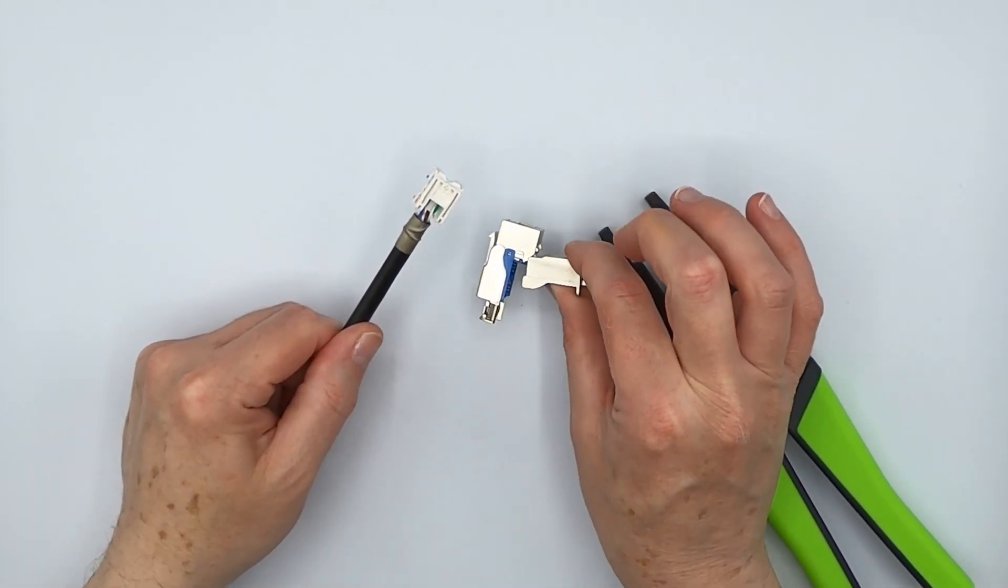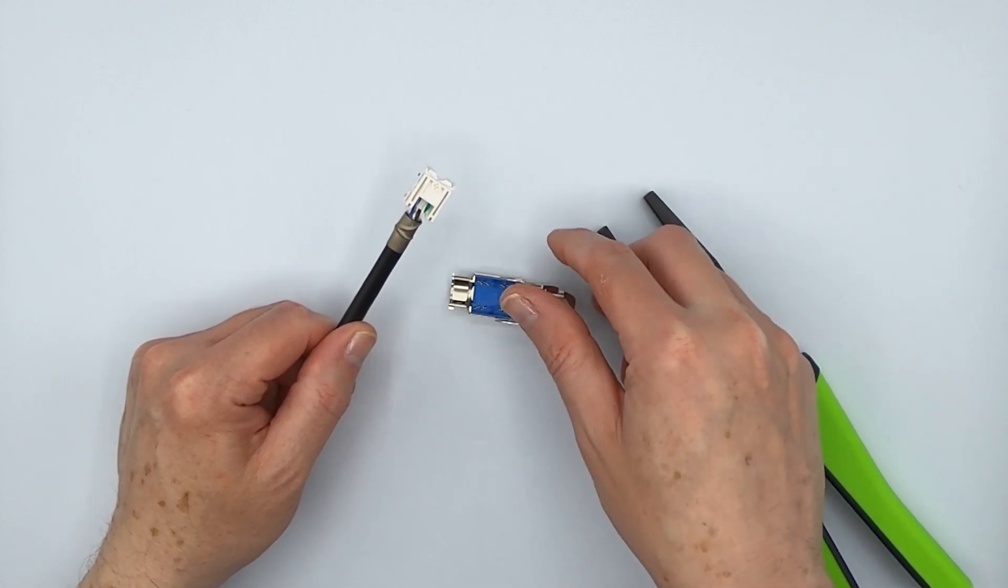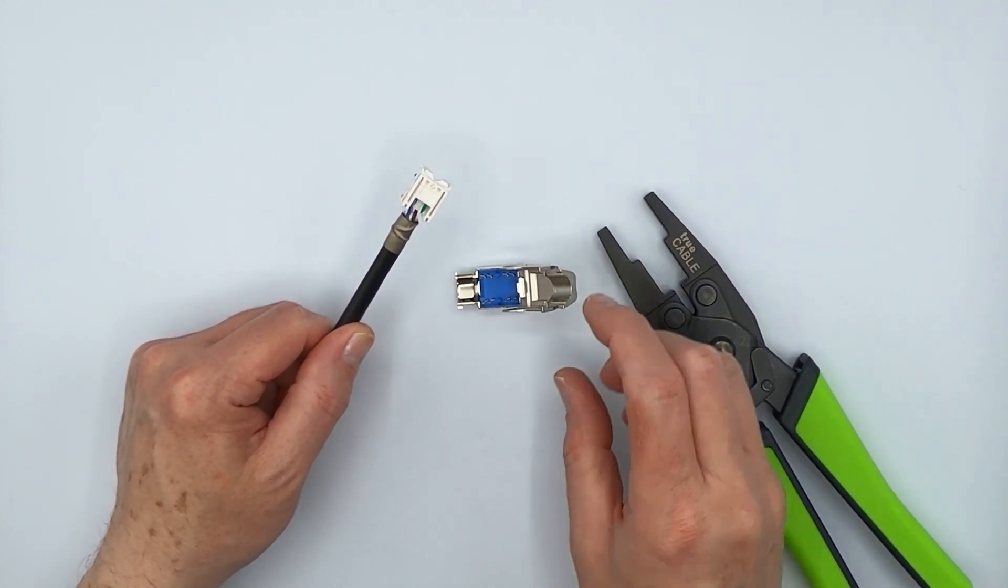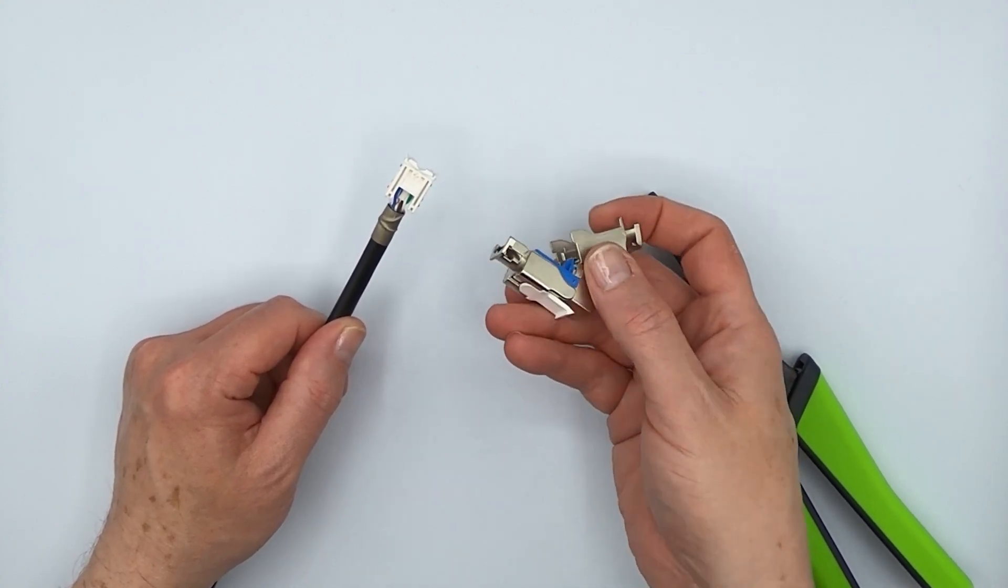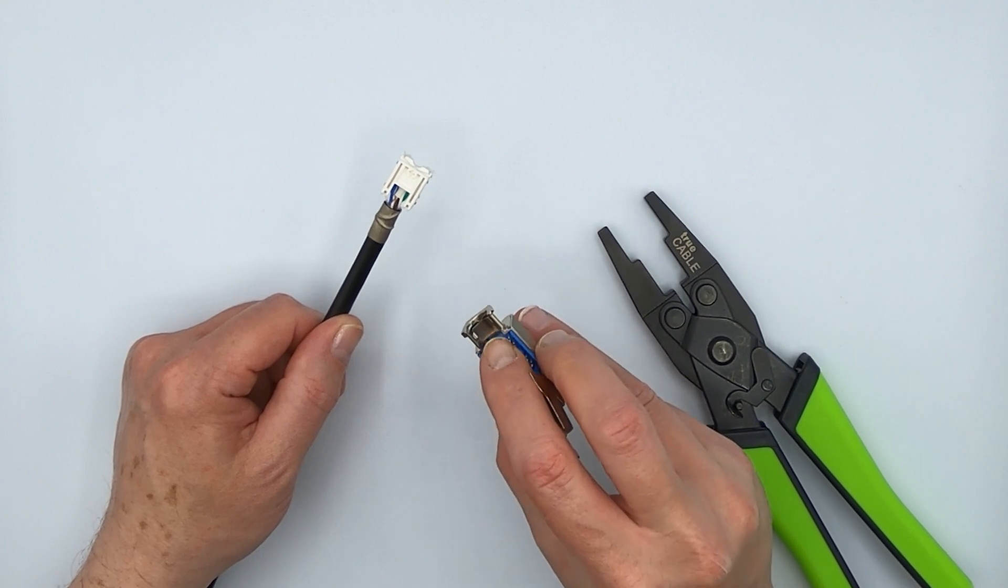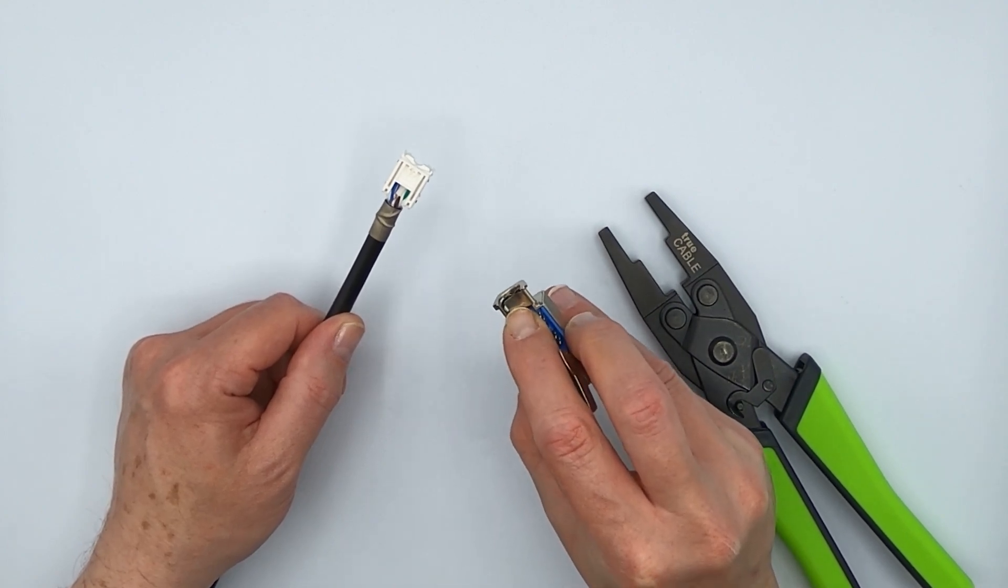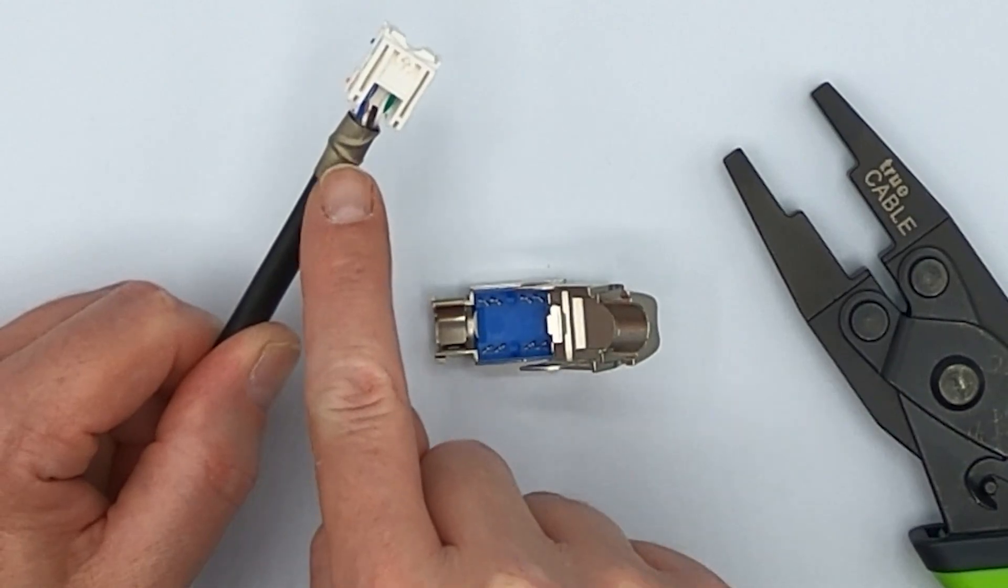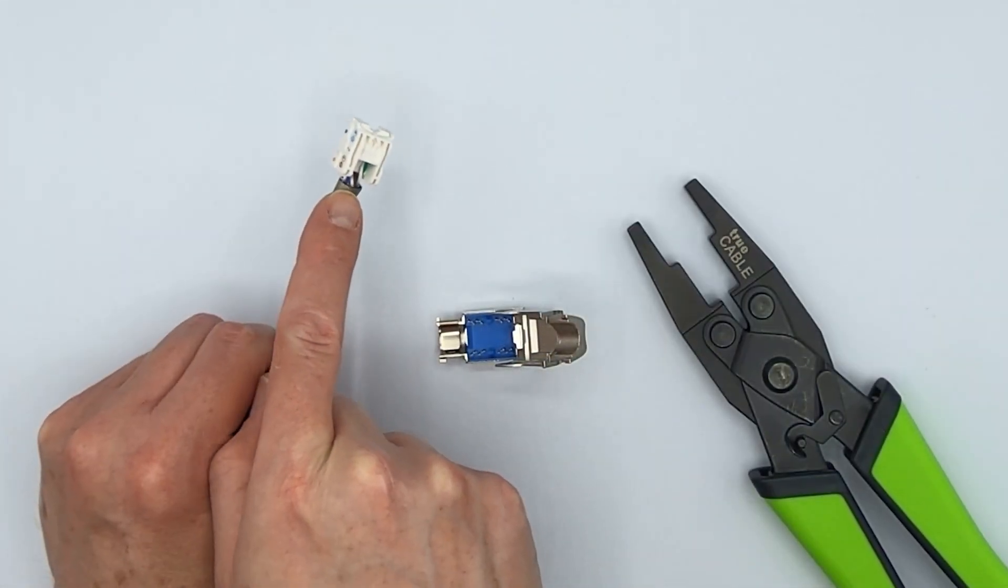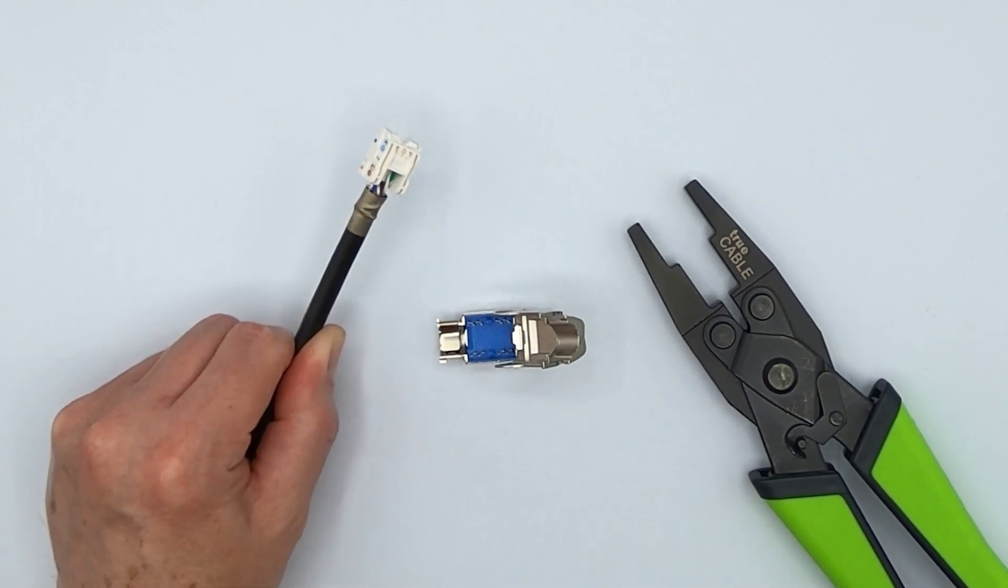Okay, so here we have a shielded toolless keystone jack. And this jack is composed of a nickel, basically a nickel plated zinc alloy. And it's got a grounding spring that's found right here. And that grounding spring needs to make contact with that copper fabric. So we take the copper fabric and we put it all the way to the edge of the cable jacket, like so.